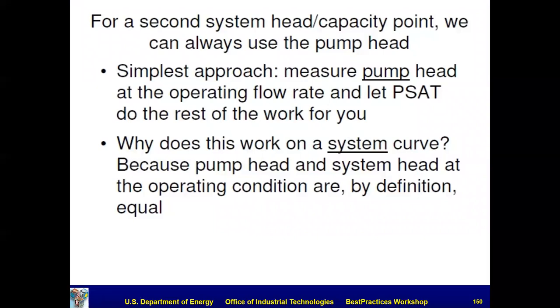Okay, let's see. So for a second system head capacity point, we can always use the pump head. Basically we need 2 points. And usually we try to take the 0 flow and the static head because that's usually really easy to do. But we have to have a second point. And if the pump is operating and you can walk up to it, a lot of times the simplest approach is to measure the pump head at the operating flow rate and let PSAT do the rest of the work for you. Why does this work on a system curve? Because the pump head and the system head at the operating point are by definition equal, because the pump curve and the system curve cross at the operating point. So you know that wherever that pump is operating has to be on the system curve.